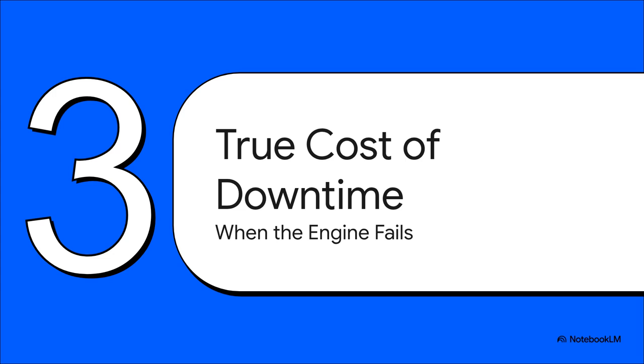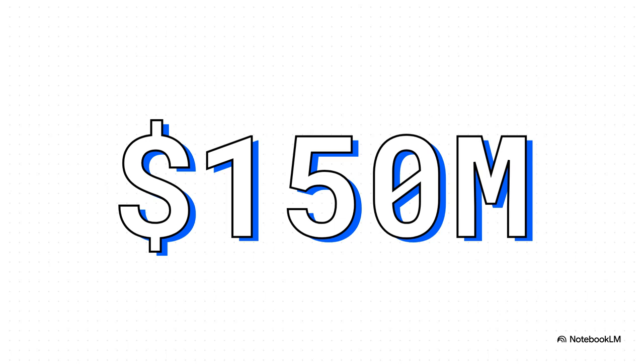With all these different facilities powering our lives, what is the actual cost when they suddenly shut down? Let's look at the high-stakes drama of offline infrastructure. To really ground this abstract concept of downtime, let's look at Delta Airlines back in 2016. They had a power loss, and their critical systems failed to switch over to the backups. The fallout? 740 canceled flights. And the estimated financial hit for that single physical infrastructure failure was a staggering $150 million.